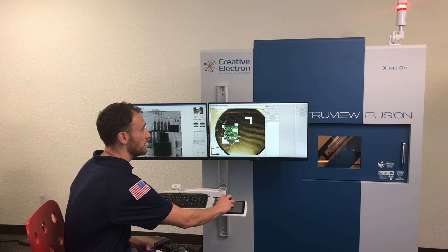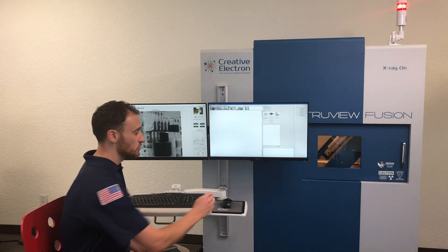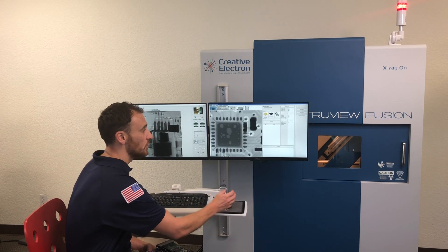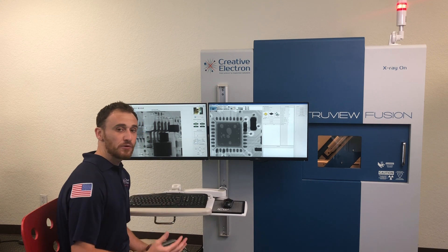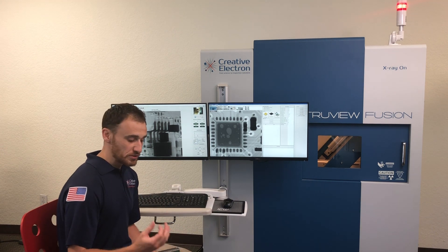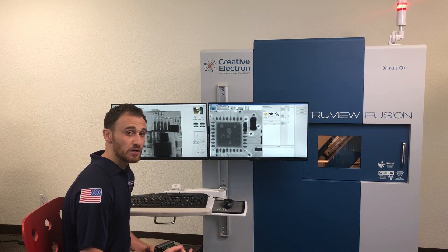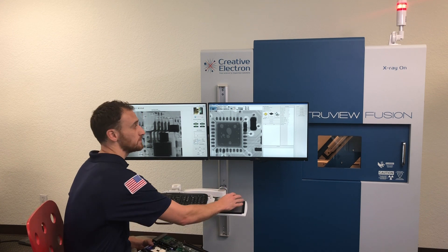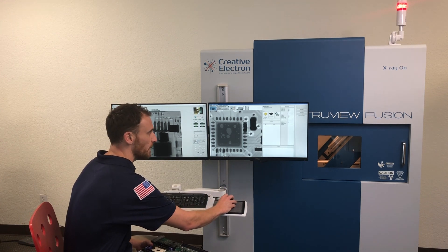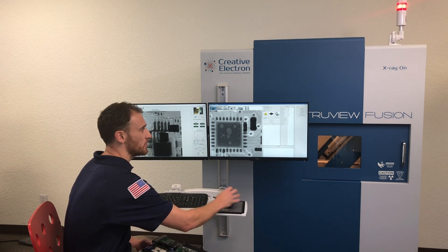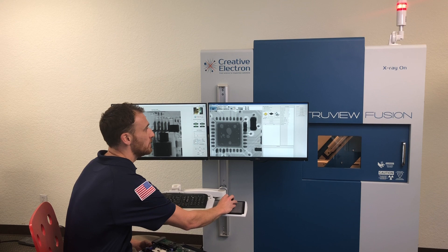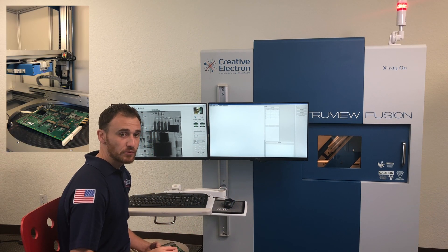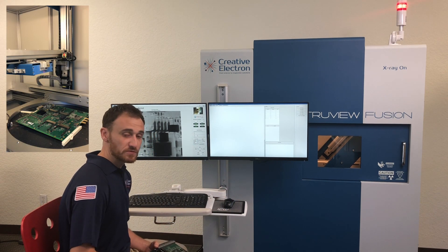The planning stage allows you to actually choose what you're gonna be looking for on each of those locations — so whether it's pad voiding, inspecting the balls on a BGA, or doing opens and shorts. You can analyze any location for those features, and then the analyzer tool will analyze each of those features.